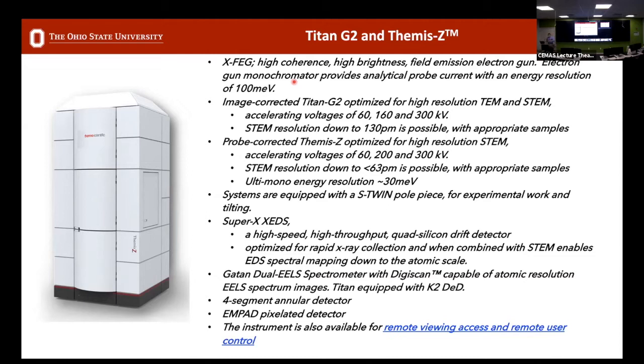Our image-corrected Titan is optimized for high-resolution TEM. We can also perform STEM at around 130 picometers resolution. We have three operating voltages: 60 kV, 160 kV, or 300 kV, so we can vary the beam energy to reduce damage to the sample while maintaining good resolution. Our probe-corrected Themis-Z is our high-resolution STEM — we converge electrons down to a sub-angstrom point. This gives us a STEM resolution of less than 63 picometers depending on the sample. With this system, energy resolution can go below 100 millielectron volts down to around 30 millielectron volts. It also operates at multiple voltages: 60, 200, and 300 kV.